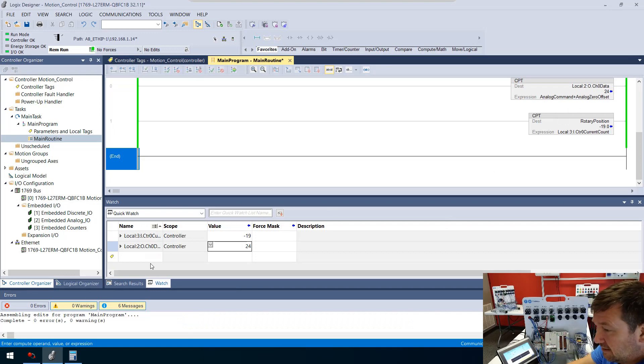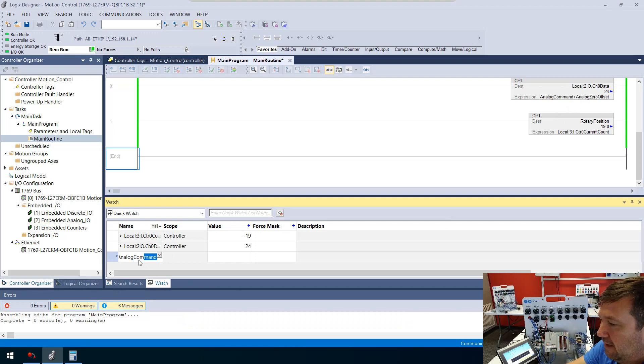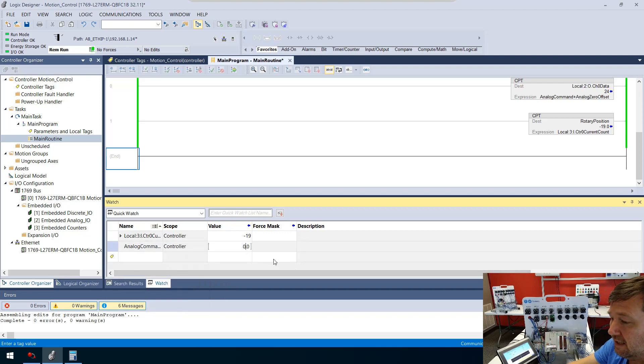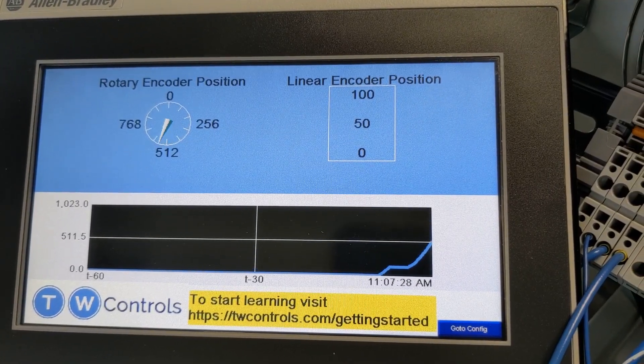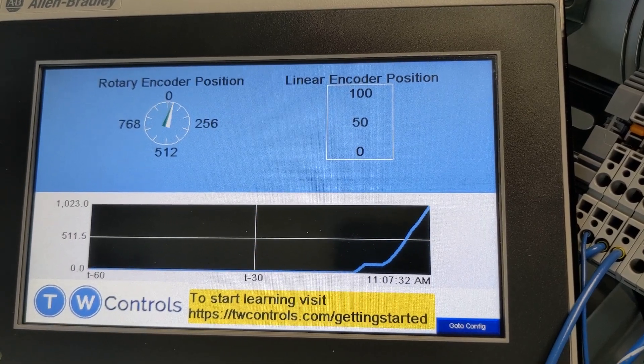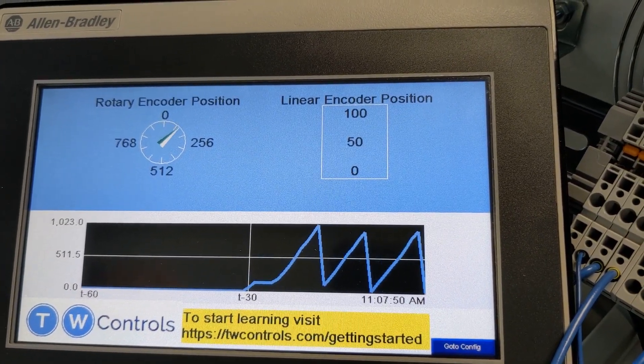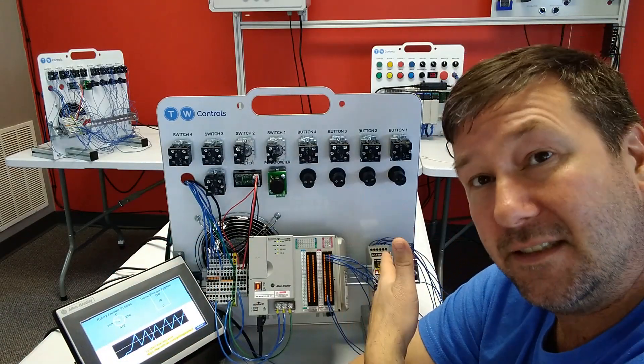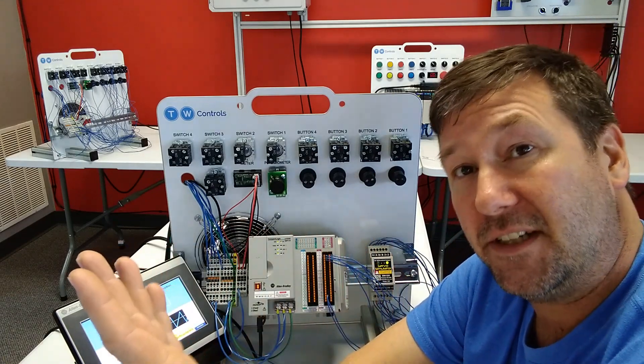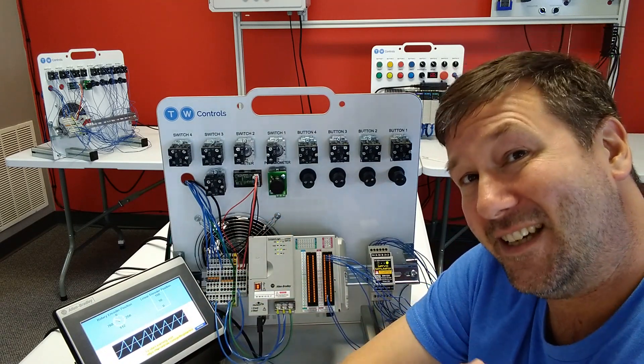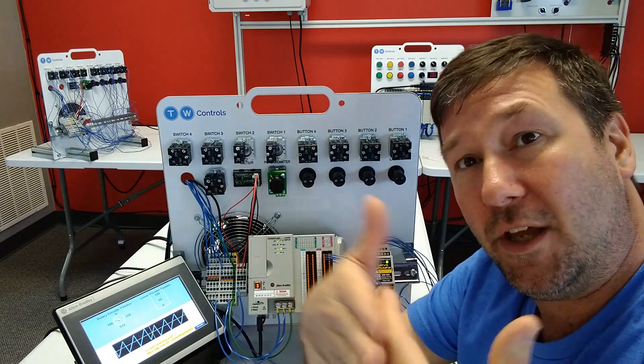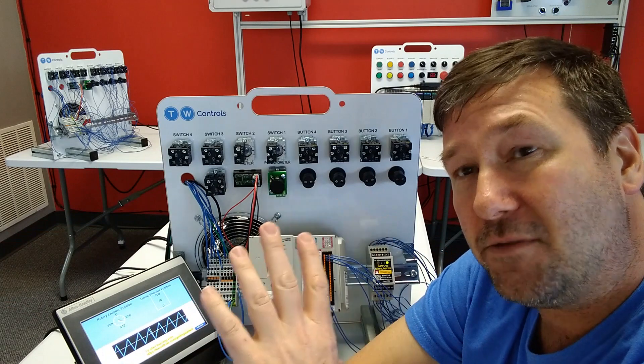In the watch window, let's add analog command. We can remove the analog channel data output entry and now let's put a value of 10 in for analog command. And there you go — now we're seeing the encoder wheel moving on our HMI. We're also seeing our value going up and then resetting at 1023, giving us a visual representation of an encoder rotating. That gets us through the basics of giving an analog command to make our servo move; a negative signal would move it the other direction. Next we're going to talk about how to turn this into something linear, because typically you're not just going to be watching a motor spin — it's going to make actual motion, like moving something from point A to point B. That's what we'll tackle in the next video.